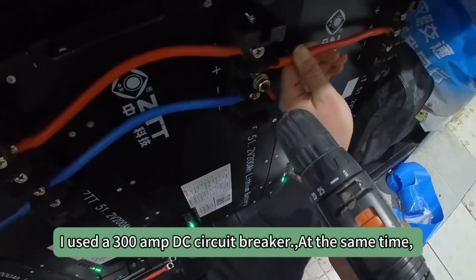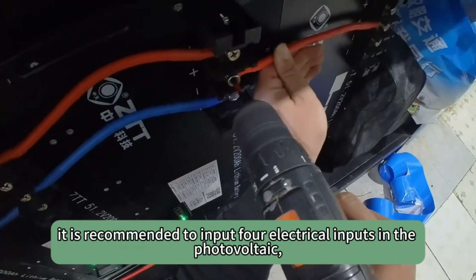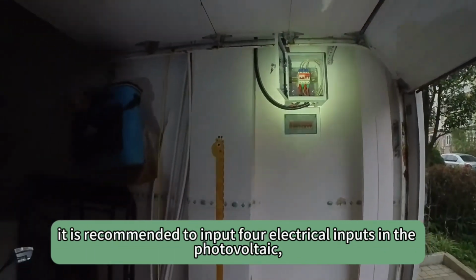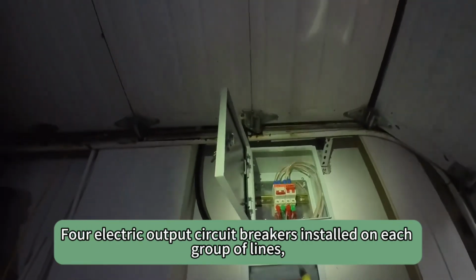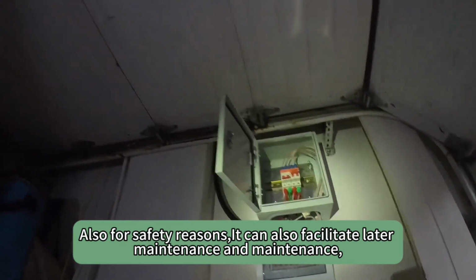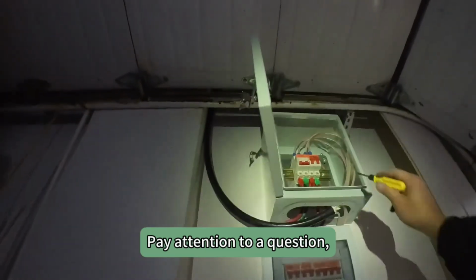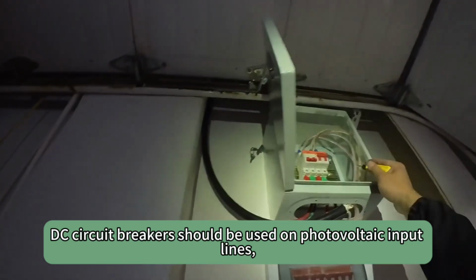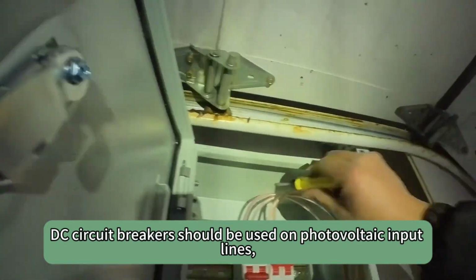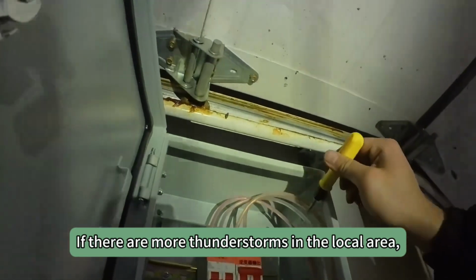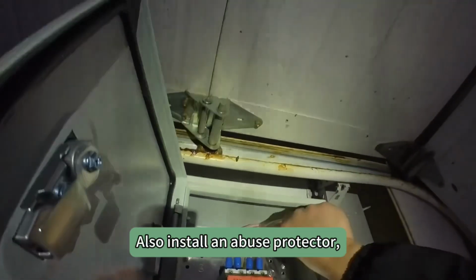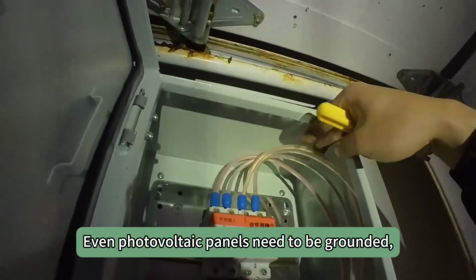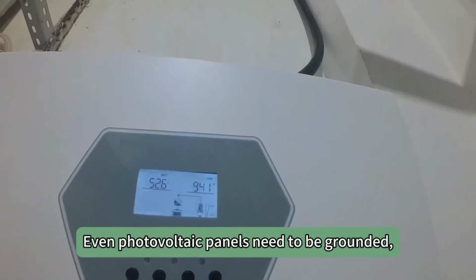At the same time, it is recommended to install circuit breakers on each group of lines, the photovoltaic input, the grid input and the output, for safety, and also to facilitate later maintenance. Pay attention to one question: DC circuit breakers should be used on the photovoltaic input lines. If there are many thunderstorms in the local area, also install a surge protector. Even the photovoltaic panels need to be grounded.